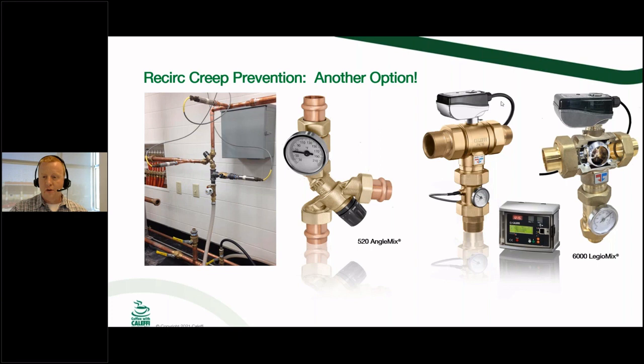But if you are working in those commercial applications, we've got our Legio Mix. This is our electronic mixing valve, and I know there were some questions in the pre-submitted about thermostatic versus electronic and things like that, but I want to talk about how this guy can prevent recirc creep. Because it is a 3-way ball valve assembly, it can actually give you bubble tight close off on either side, hot or cold if necessary. So you don't have to go through all the trouble of the globe valves and the balancing in the very specific scenario where you've got no demand from your fixtures. You can just pipe this in and you're good to go.